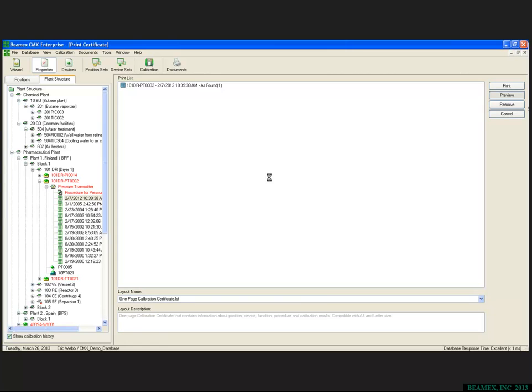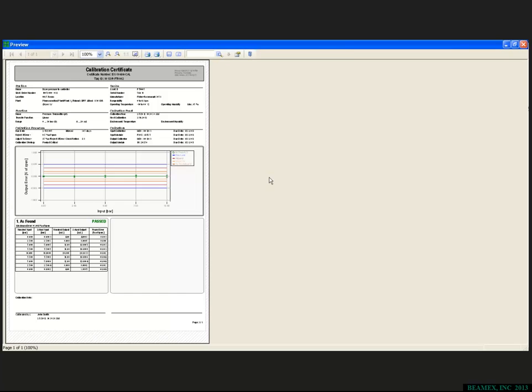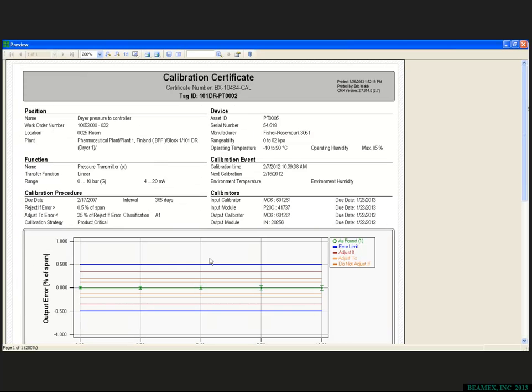Okay, Eric, it looks like we have another question here for you. Can you repeat the rules of thumb for the increase or decrease calibration frequency based on the past calibration history? And that question is coming in from Richard. Sure. The rule of thumb would be if you have 3 successive calibration intervals where that particular asset met its calibration tolerance each time, meaning there were no out of tolerance values recorded for any period during those 3 calibration cycles, that would typically justify increasing the calibration interval by 50%.